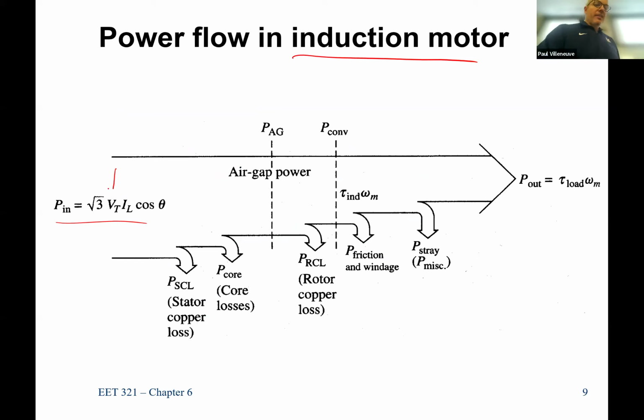Remember, this is almost always given to you as a line quantity, so that would be the voltages across 2 lines. So this equation is written as terminal voltage. Whenever you see the nameplate terminal rating, the voltage rating on the nameplate of a transformer or an induction machine, the 480, the 4160, that's a line voltage. A lot of motors are actually dual rated so you can run them at a couple different voltages, but those would still be line voltage parameters.